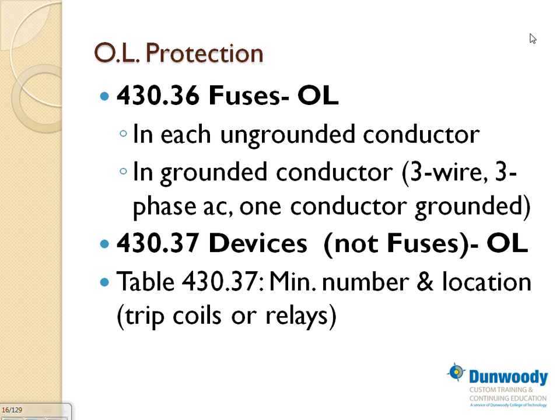You can use a fuse as an overload, in each ungrounded conductor. Can I use a fuse as an overload? Yeah, you can use it, but typically we don't use a fuse on major motors as an overload. You have a separate overload as part of your starter to protect the motor, which is better protection. But for a smaller motor, you can use a fuse, and then you have to put it in every ungrounded conductor.